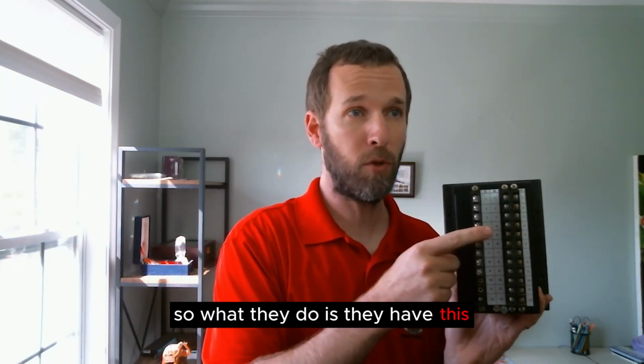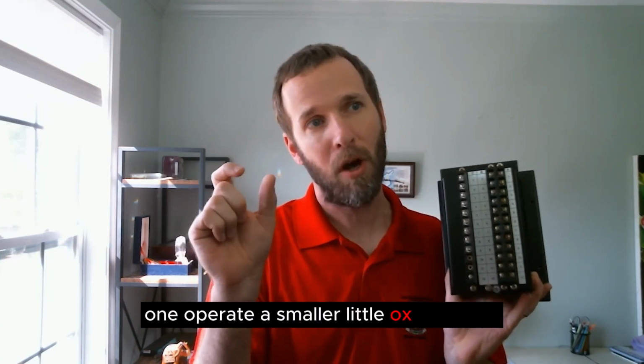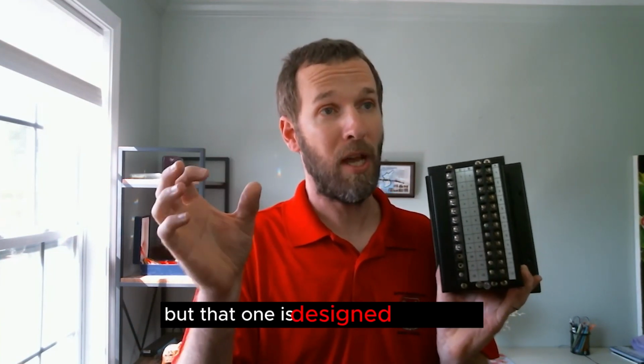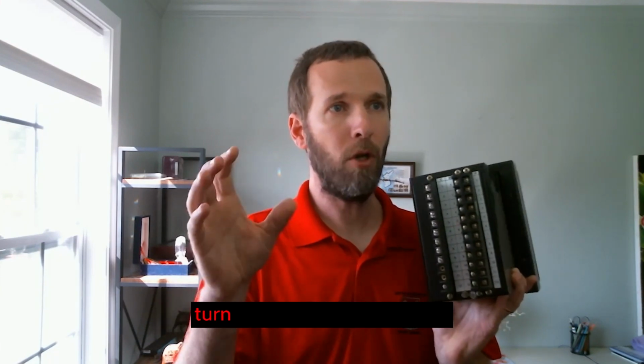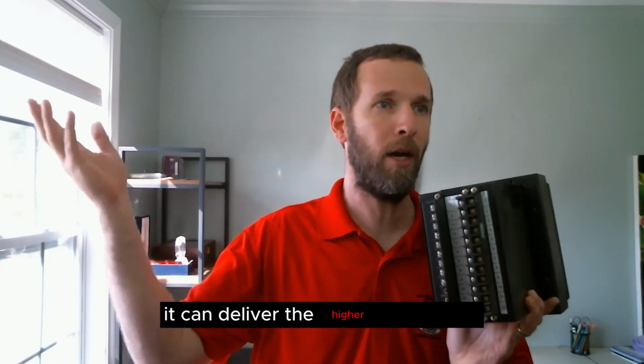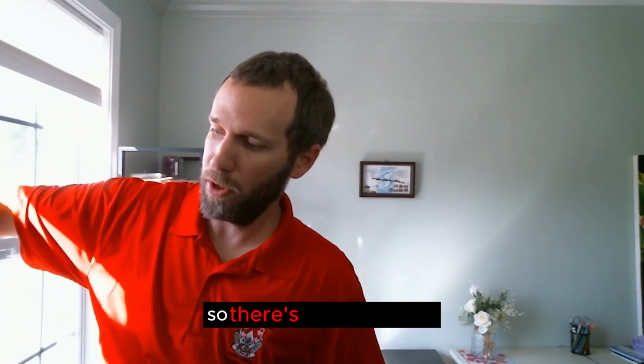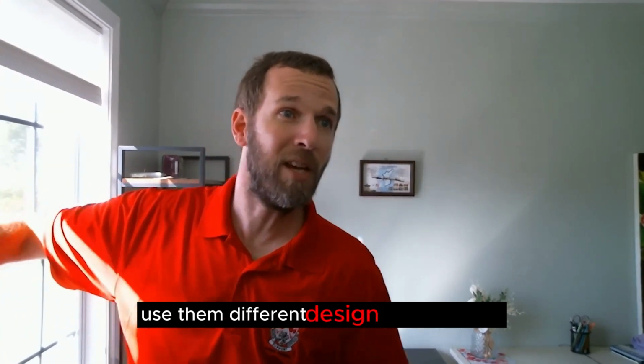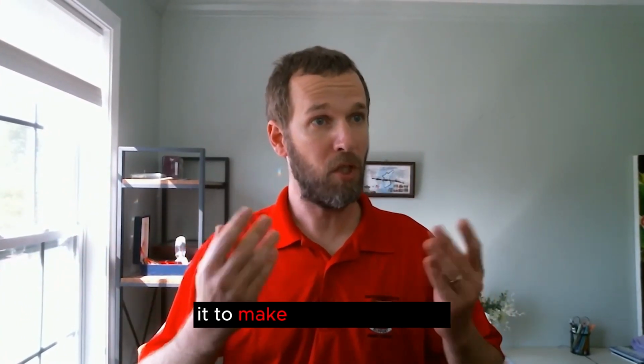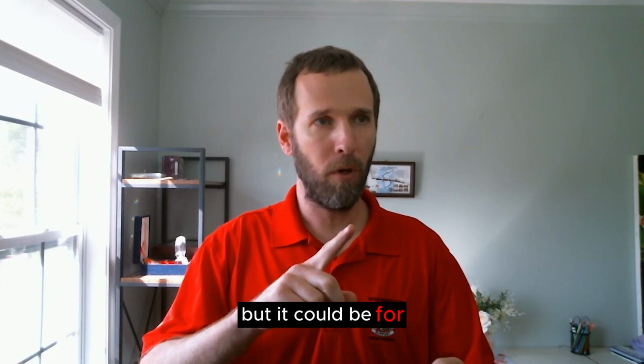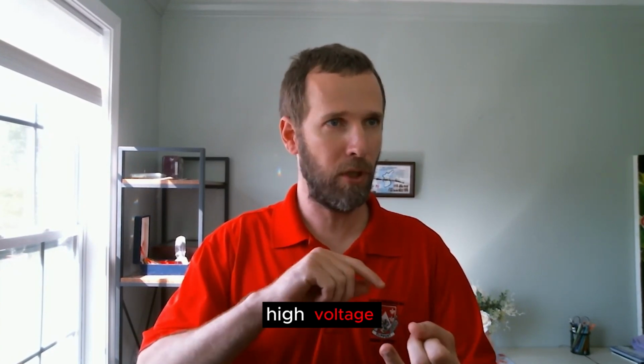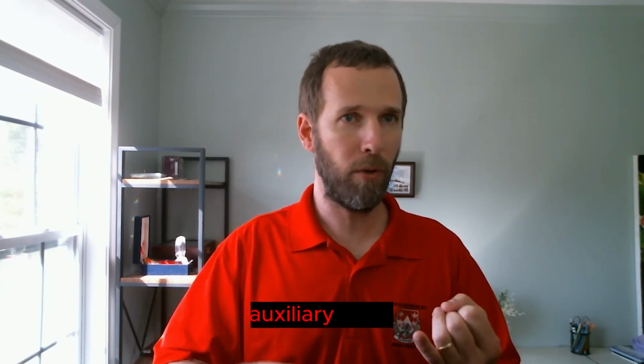So what they do is have this one operate a smaller aux relay, but that one is designed only to turn on, and when it turns on, it can deliver the higher current. So there's different relays using different design concepts to make the scheme work - it could be for low voltage, medium voltage, high voltage, protection-based, auxiliary-based.